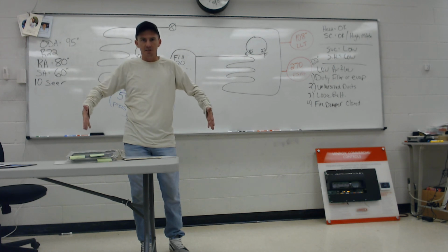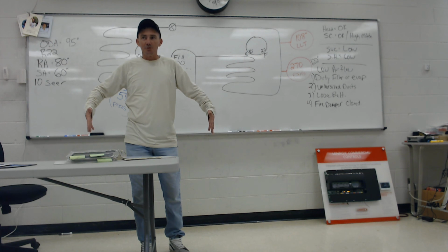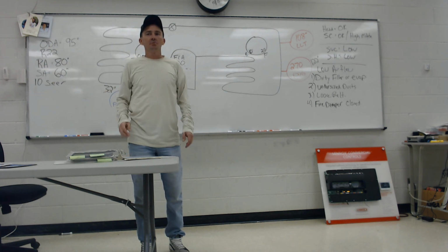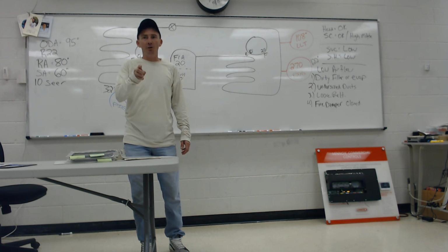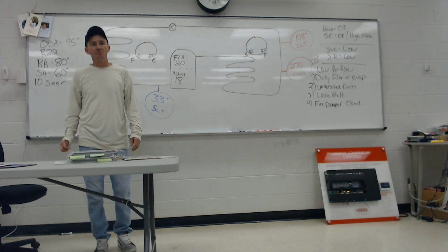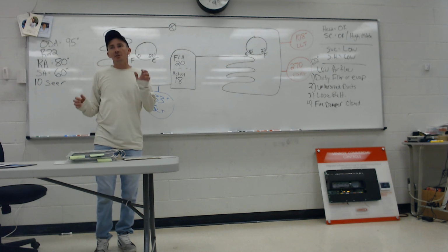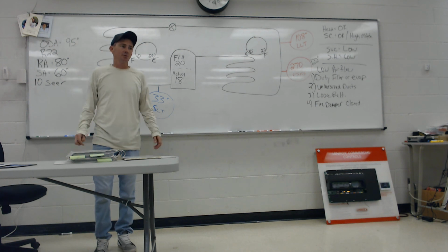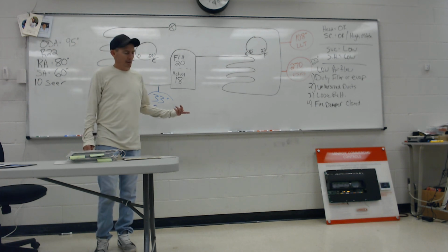The insulation inside of a furnace, you take the doors off, it looks fine. Then you put the doors on and it starts sucking the insulation up against the motor or the blower wheel, and it'll block the blower wheel. That one will burn you. Anyone get burned by that one yet? Everything looks peachy in here, but as soon as you start putting the doors on, you can't see anymore, and it sucks the insulation up against the blower, and it will burn you.